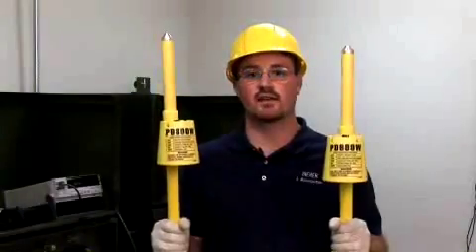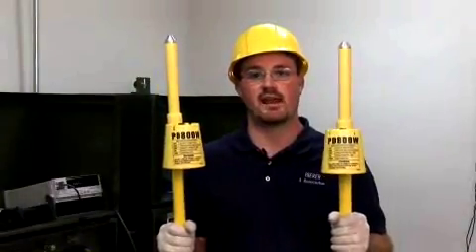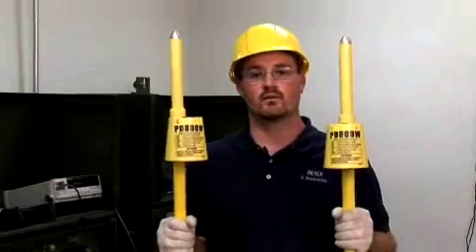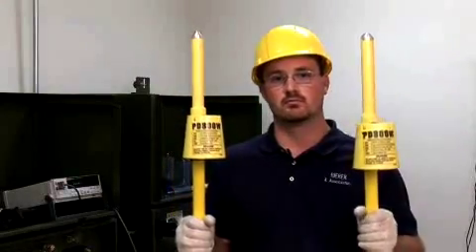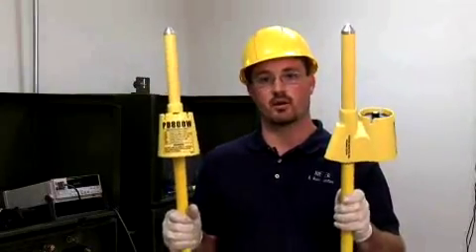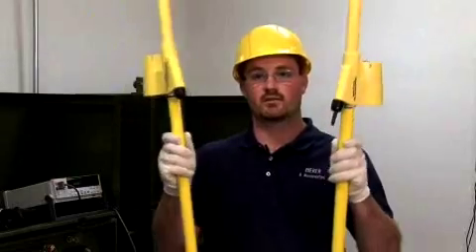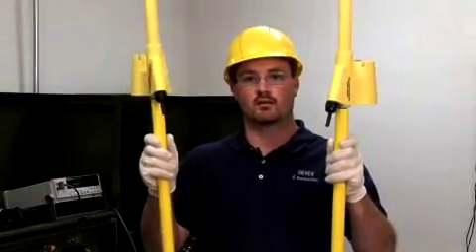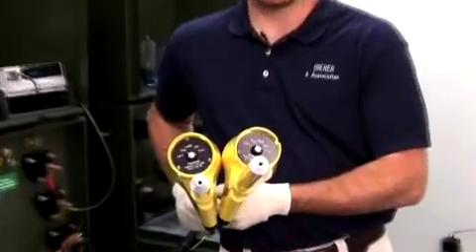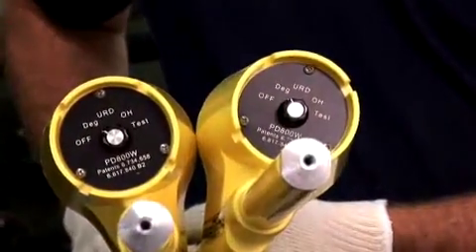This is our cordless phasing tool, part number PD800W. What we've done is eliminated the cable between the reference probe and the meter probe. We've replaced it with two antennas that communicate wirelessly from one probe to the next. The back plates on the two probes are exactly the same.